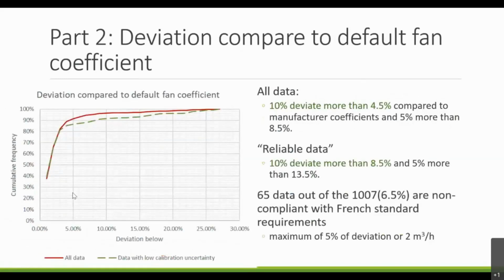We have also plotted the deviation compared to default coefficients with whole data in red and only data with low calibration uncertainty. That means with the capability index above 3. And in fact, we found out that data with low calibration uncertainty have higher deviations than whole data, which means that if we take only reliable data, it deviates more than whole data. So in fact, the deviation we observed here is not due to the calibration uncertainty, and there is really a deviation of the fan that appears after years.